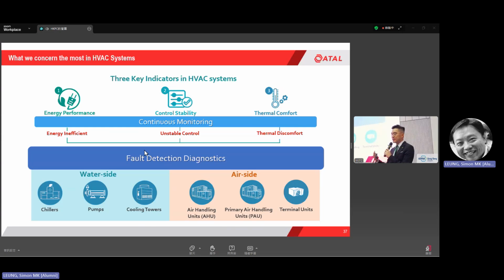Because the HVAC system uses PID control, the chillers will provide a stable chilled water supply temperature. For the AHU, it provides a stable supply air temperature. It runs the PID control loop. If the system is unable to provide the set point, that means something is wrong with the system. With high frequency data, we can diagnose the fault related to the PID. So that is the power of high frequency data.